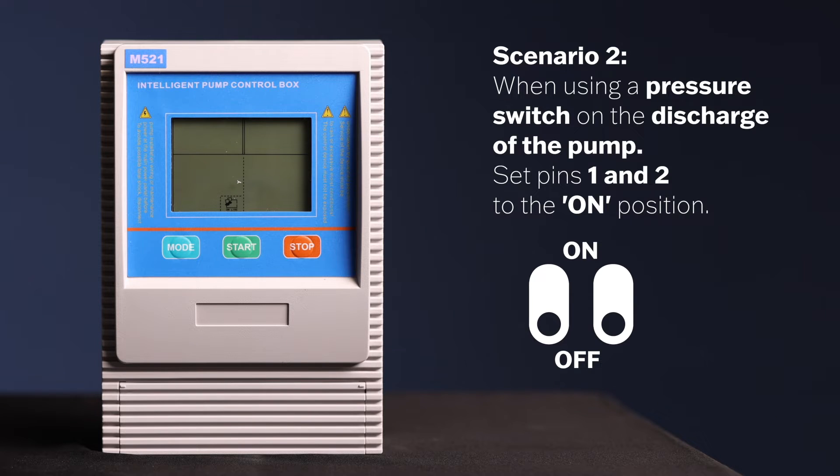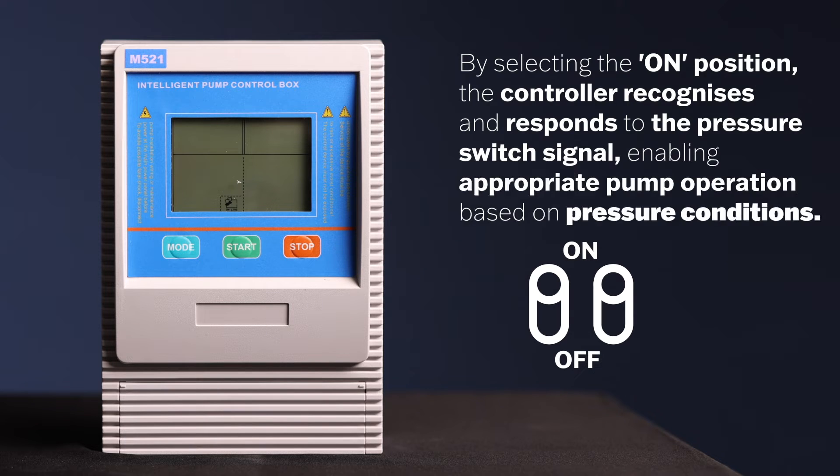Scenario 2: When using a pressure switch on the discharge of the pump, set pins 1 and 2 to the ON position. By selecting the ON position, the controller recognizes and responds to the pressure switch signal, enabling appropriate pump operation based on pressure conditions.